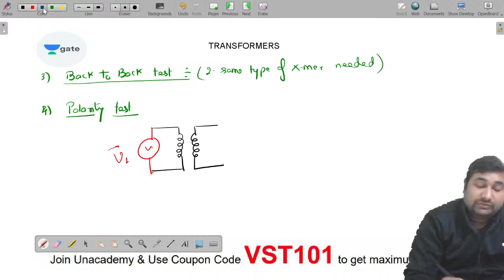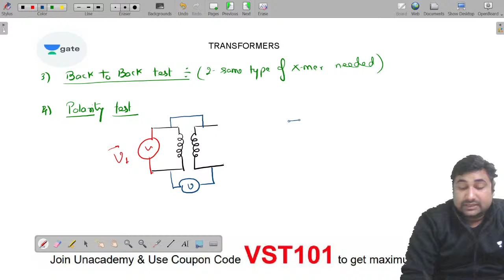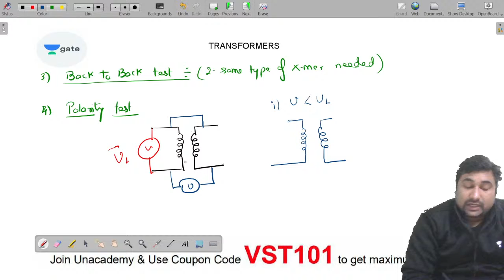We only have to use a voltmeter here. If this voltmeter reads lower than V1, this suggests that these two are of the same polarity. It is very easy to understand — you just follow the voltmeter reading. Here I am connected on the HV side of the transformer. If the voltmeter reading is less than V1, this suggests that the terminals where the voltmeter is connected are of the same polarity. So either you can represent the dots at this point, or at this point.